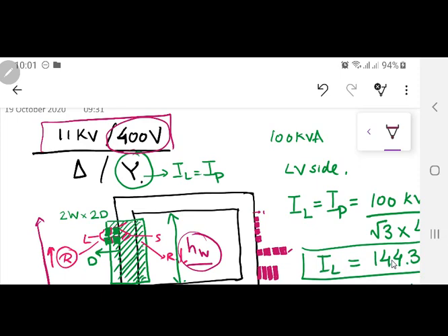Okay? So when the charging of the capacitors takes a huge amount of current, a spiky current, that spiky current is going to change very fast, and it is passing through the inductance of your transformer or whatever coil is there. It's going to have a very large voltage spike. That voltage spike is going to be detrimental. Now supposedly this is an 11 kV transformer just outside your home. It is just a 100 kVA size, and incidentally the light comes, and incidentally all 20 houses which are connected turn on their air conditioners.